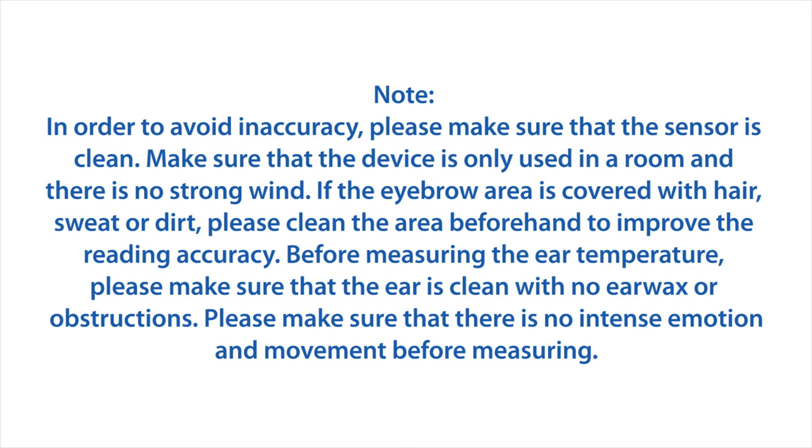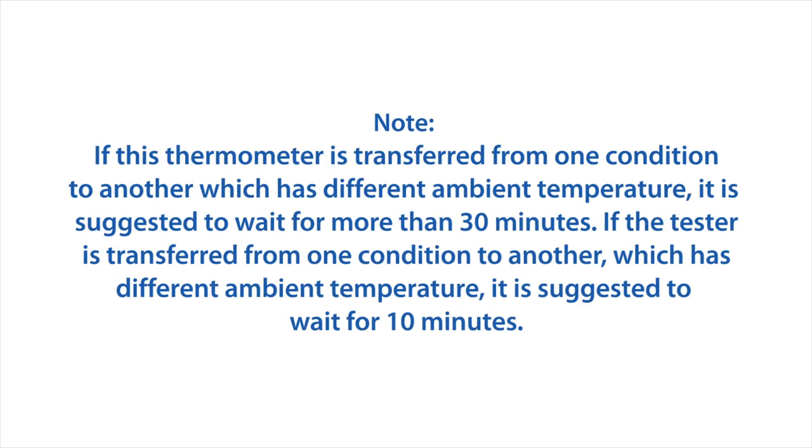Before measuring ear temperature, make sure the ear is clean with no earwax or obstructions. Make sure there is no intense emotion or movement before measuring. If the thermometer is transferred from one ambient temperature condition to another, wait more than 30 minutes. If the tester is transferred between different ambient temperature conditions, wait at least 10 minutes.